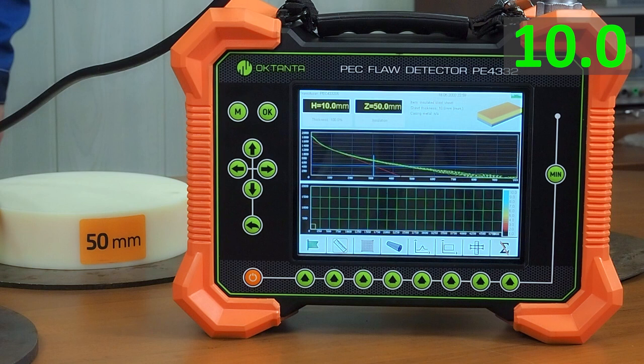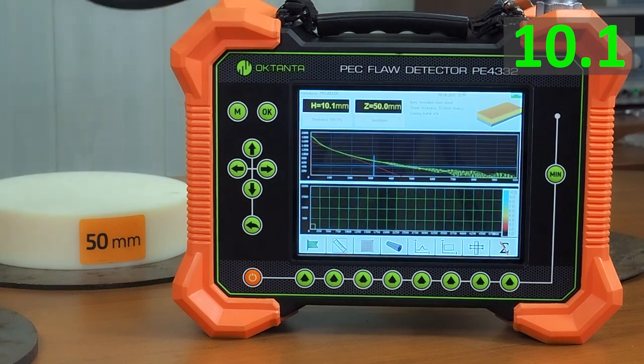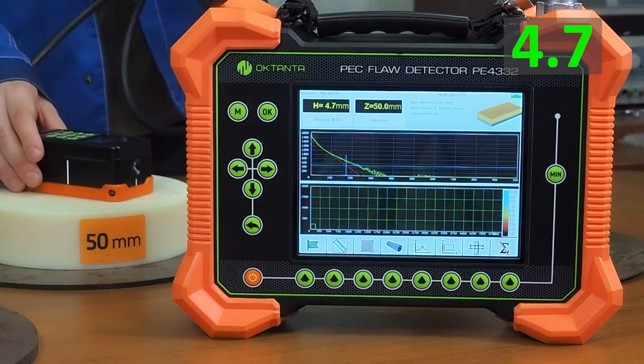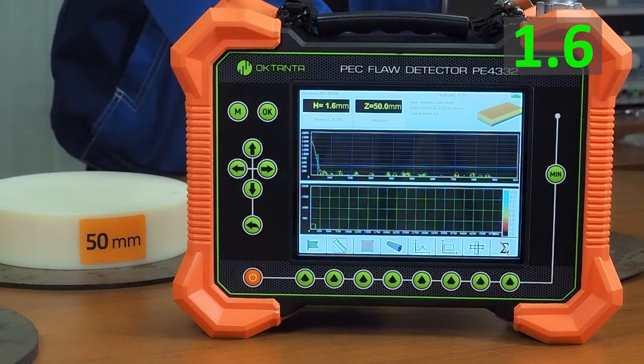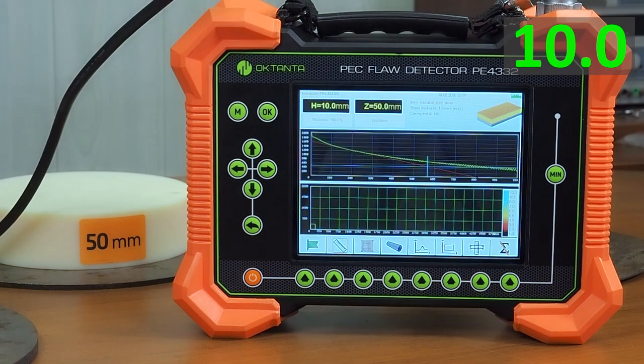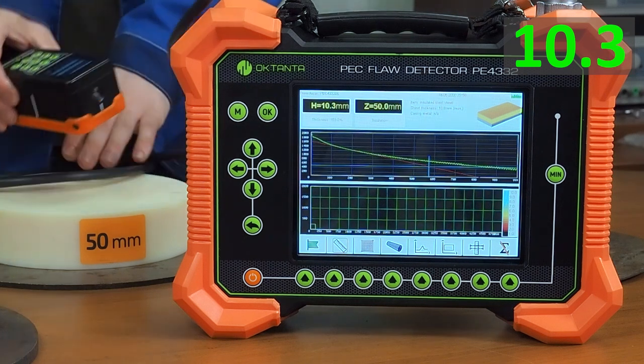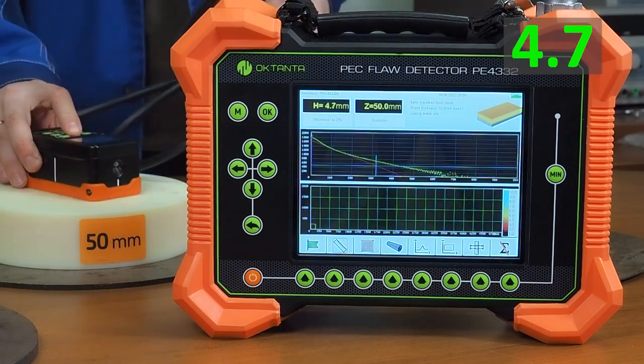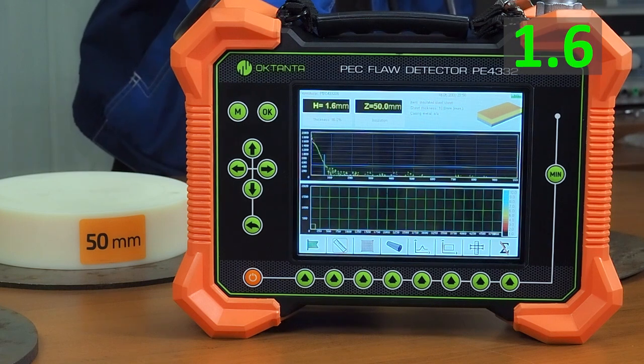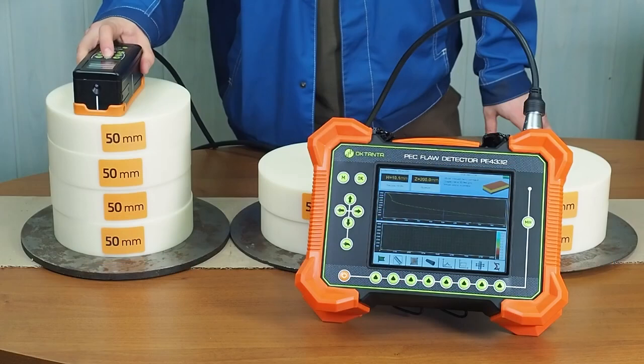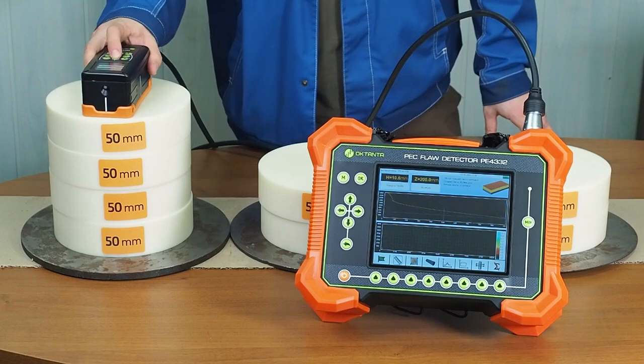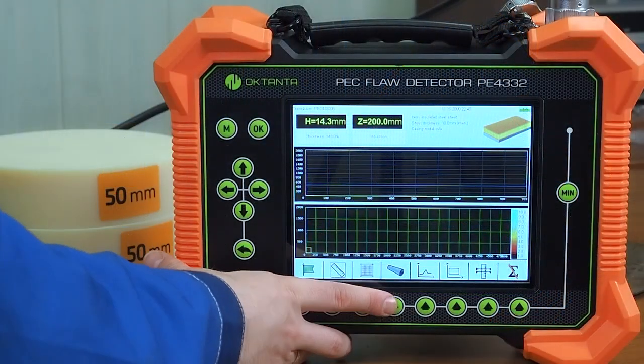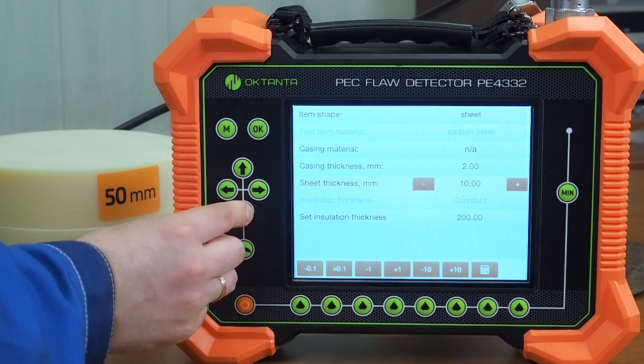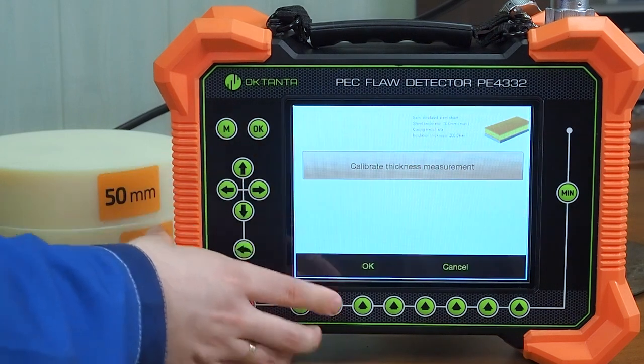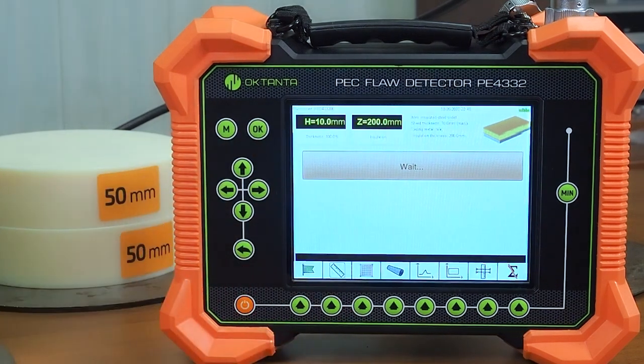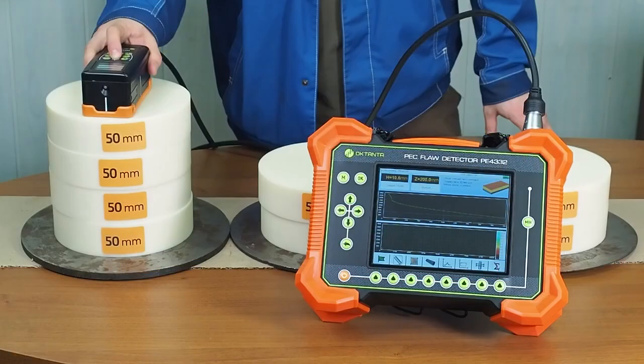As the device doesn't measure directly the wall thickness, the thickness measurement accuracy is 10%. However, in practice, we see good reproducibility of results both for 50 mm and for 100 mm thick insulation and an obvious change of the demagnetization diagram and measured wall thickness in such areas where the pipe thickness actually changes. For insulation thicknesses up to 200 mm, use a middle-size sensor. Don't forget to calibrate. The demagnetization curve depends on the insulation thickness, so it is important to set the correct calibration parameters for correct calculation of the test object wall thickness.